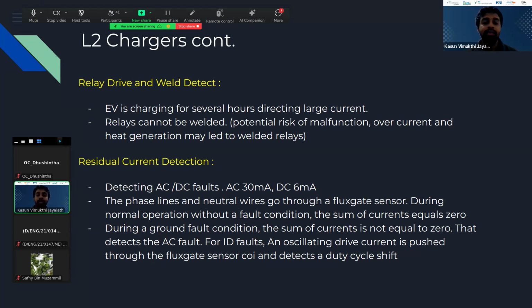The standards say that for AC, if the sensor detects a 30 milliampere residual current, it should stop. For DC, if there is a 6 milliampere leakage or residual current present in the wire, it should also be detected.